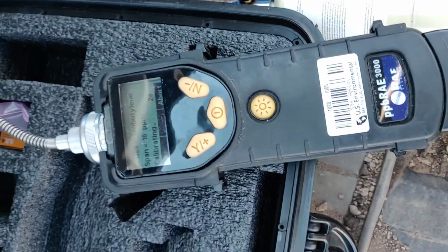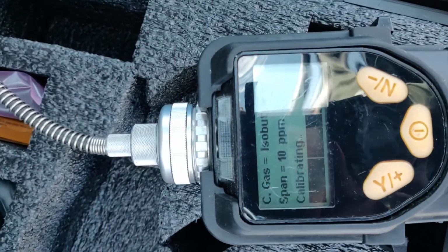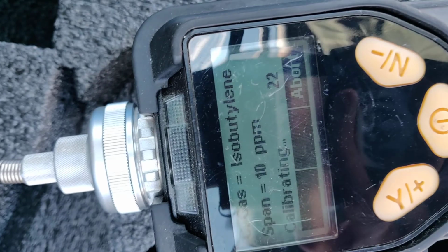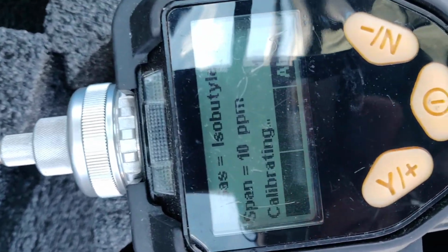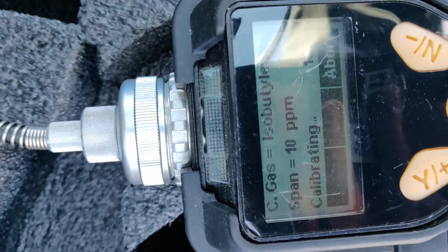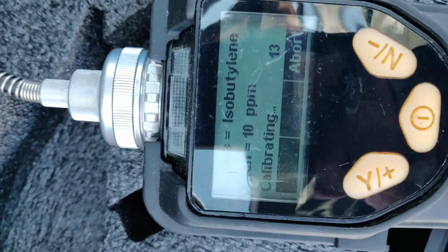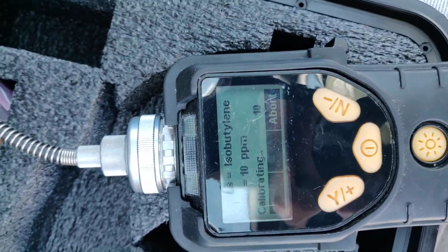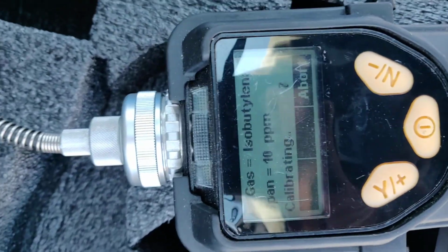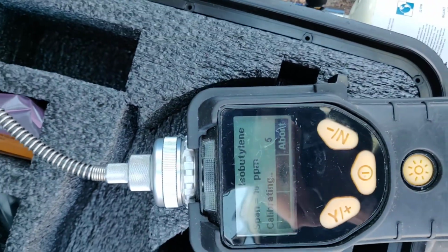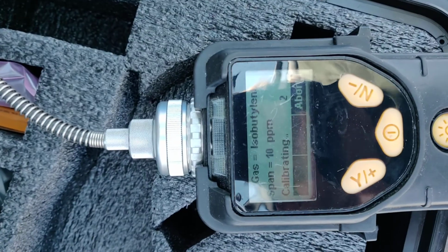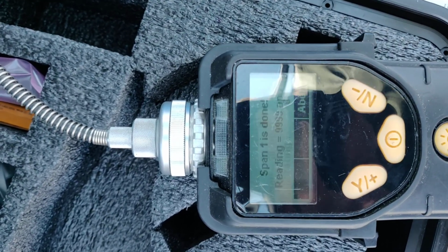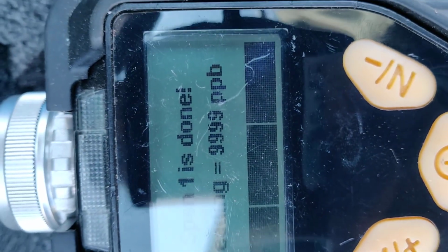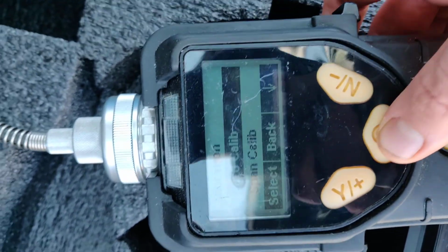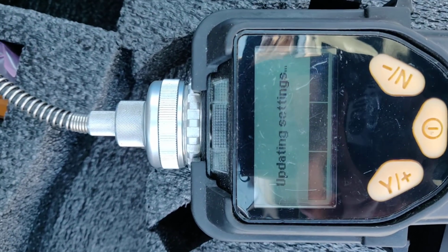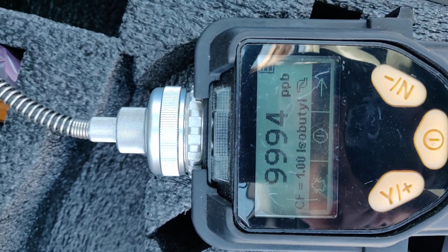Yes. Alright, so like I said, you're setting a baseline, a zero, and then a mid-range point, and then you'll have a linear relationship of concentration of volatile organic compounds in the air versus what it's measuring. What is it actually measuring? It's measuring a voltage, because it has an ultraviolet lamp that emits a consistent amount of energy. See? 10 parts per million, really close to 9999 PPB. Alright, and I just go back, updated settings, see it's holding a steady reading, which is good.